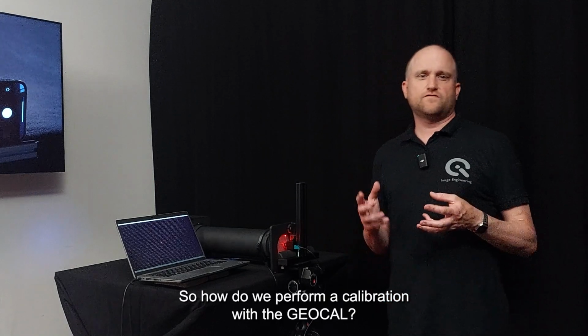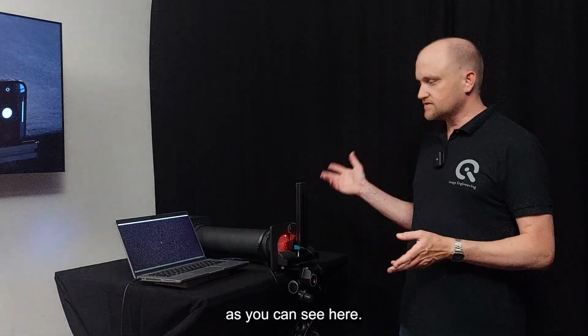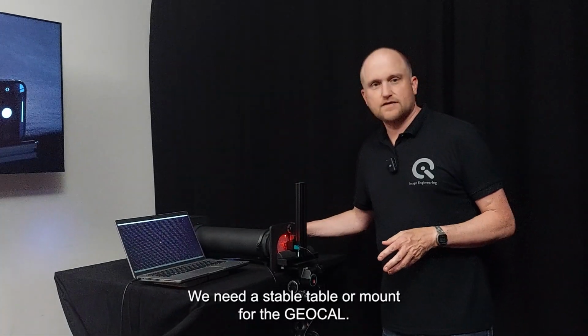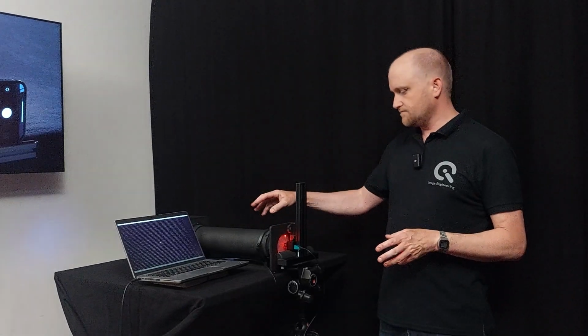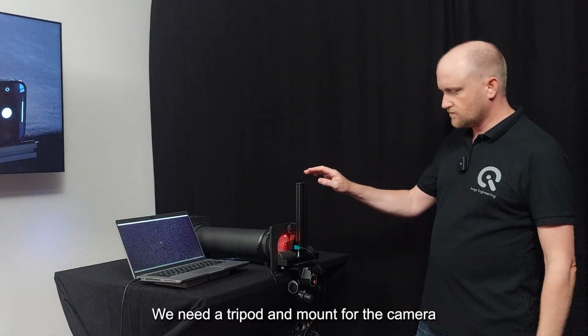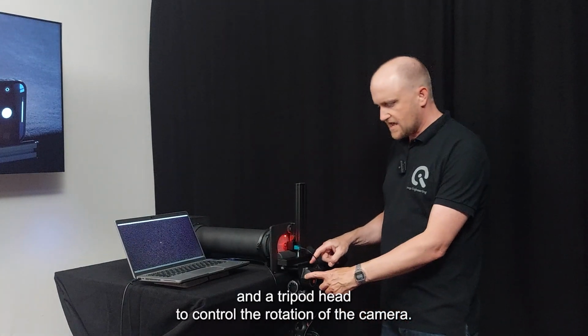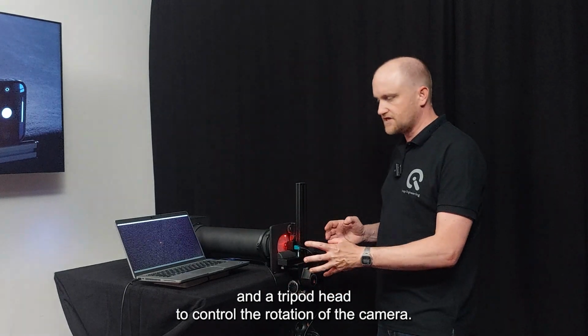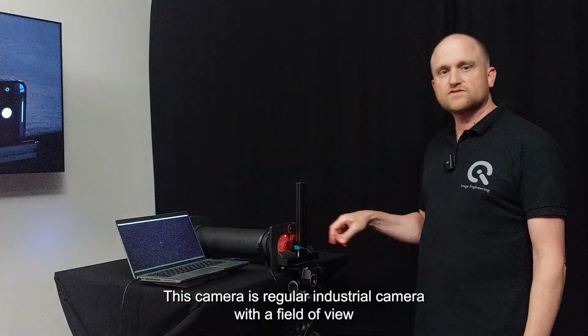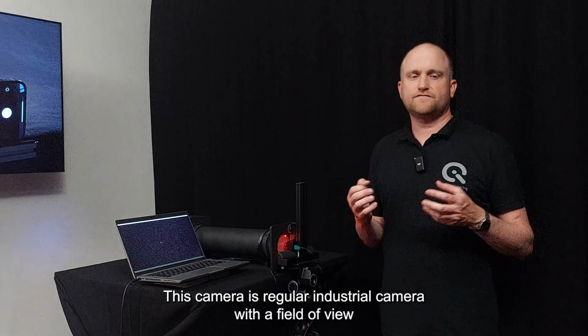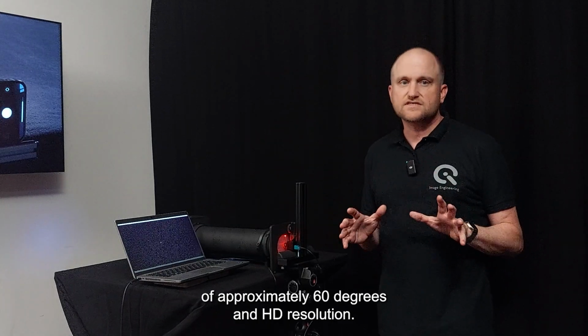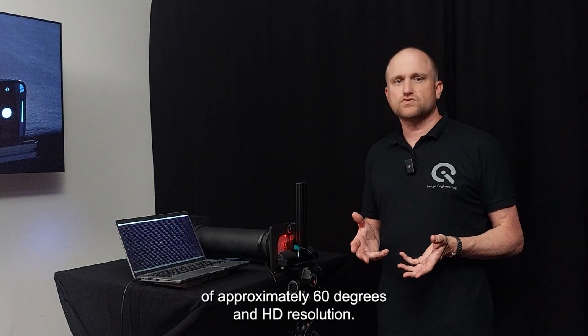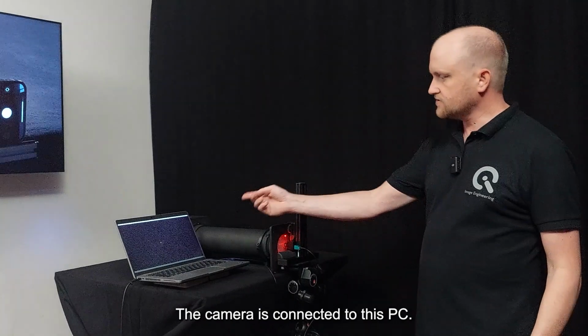So how do we perform a calibration with the GEOCAL? The setup is very simple, as you can see here. We need a stable table or mount for the GEOCAL. We need a tripod and mount for the camera and a tripod head to control the rotation of the camera. This camera is a regular industrial camera with a field of view of approximately 60 degrees and HD resolution. The camera is connected to this PC.